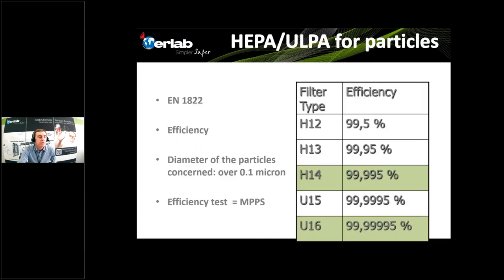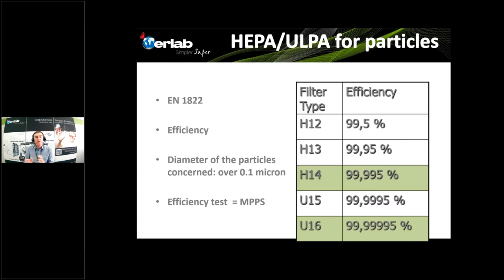The standard used to determine HEPA and ULPA filter performance is EN 1822. There is also an equivalent standard in the US. You will see small differences in efficiency values between the American standard and EN standard, but they are very similar.